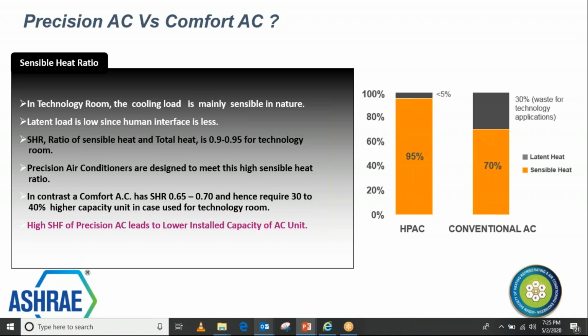Which means that the air conditioning system you deploy in such an application should be designed for high sensible cooling. This is very important to understand. Suppose it is not designed for high sensible cooling, what happens there? Your comfort air conditioner, which is designed for only 60 to 70% sensible cooling, imagine that you need to install a 10 TR capacity there. 10 TR is your load for your control room, which has, let's say, a 0.95 sensibility ratio. Sensibility ratio is, I think most of you are from an air conditioning background, so you know, sensible to total capacity. So here the sensible load is, suppose, 0.95, or 95% sensible cooling is required.